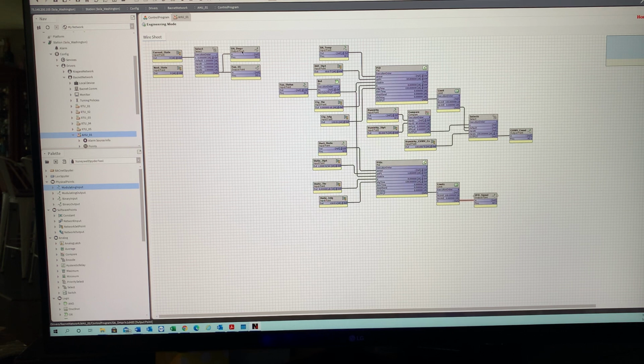We could take the outdoor air damper, look at space or return CO2, and modulate the outdoor air damper based on CO2. That way you're not opening the damper 100% when there's no need for it, when everything in the background is doing well, and you're not bringing in all this humidity.